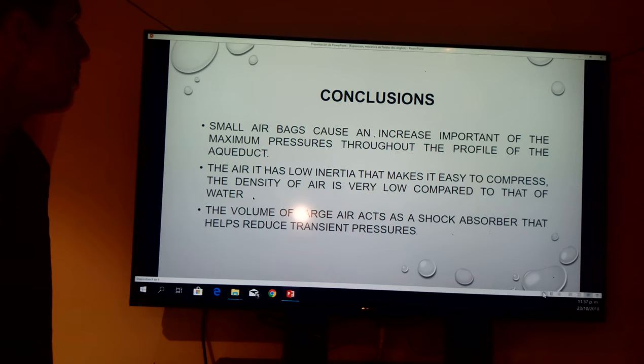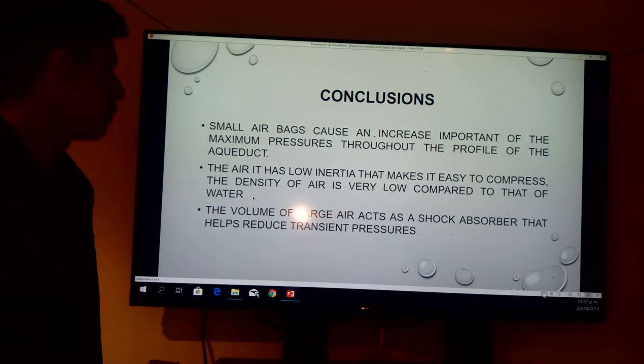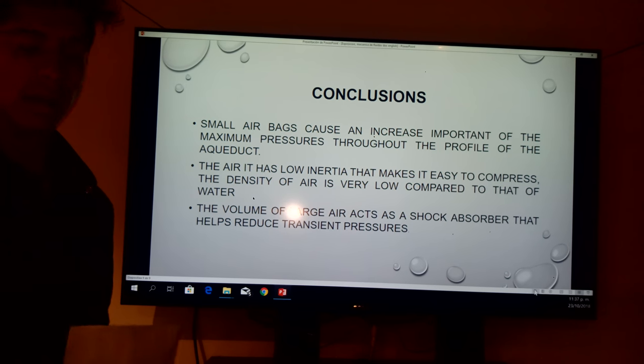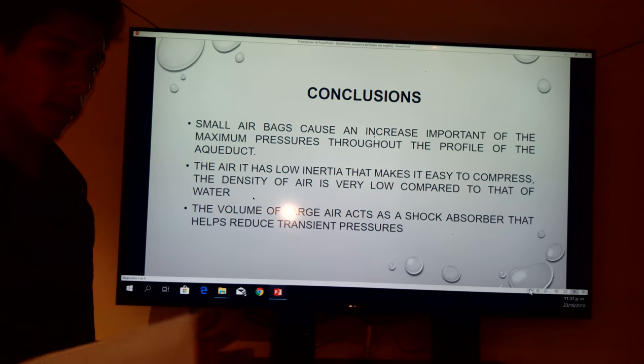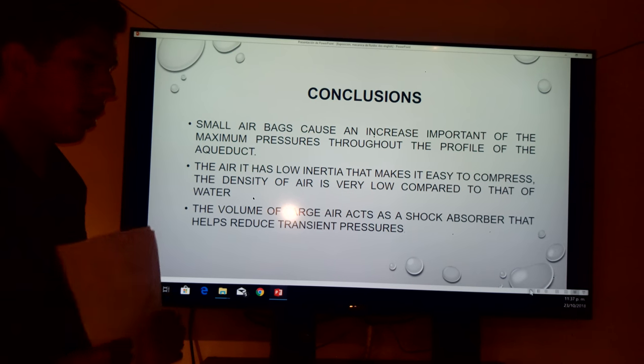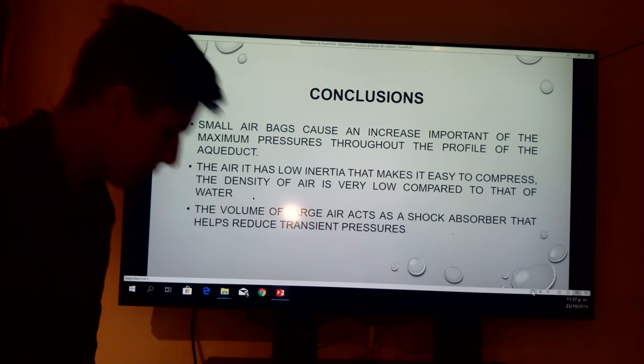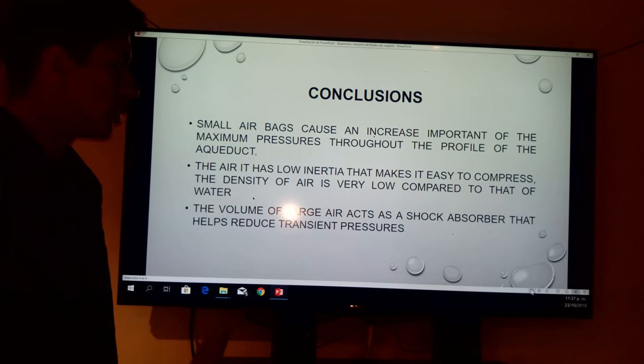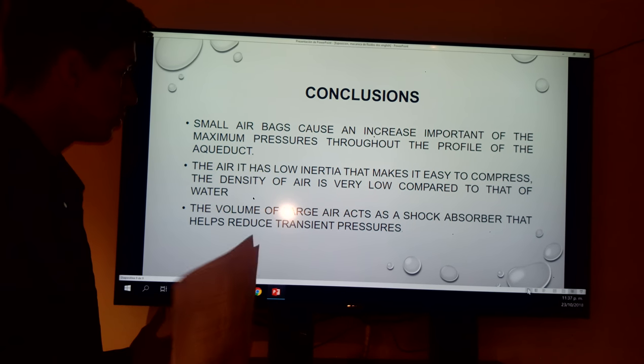Conclusions: Small airbags cause an increase in the maximum pressure throughout the profile of the aqueduct. Air has low inertia that makes it easy to compress. The volume of air acts as a shock absorber that helps to reduce transient pressures.